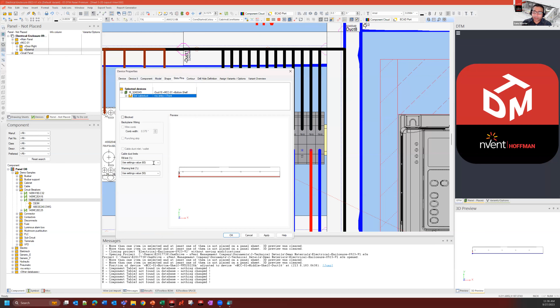Now, how do I know that? You can set it as a project setting, or you can set it up inside your duct to say, okay, my fill limit is 60%. So if the duct is 60% full of wires, stop using that duct. Or give me a warning at 50% and then stop at 60. You can manipulate that any way you'd like, so you can be sure your ducts are not too full.